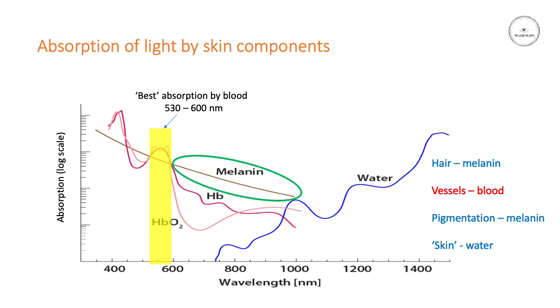If you want to treat hair, then you will target the melanin typically at this part of the spectrum — everything above around 600 nanometers. And this will, as you can see here, be preferentially absorbed in the melanin, but not so much in the hemoglobin or deoxyhemoglobin. So there's less chance of damaging blood vessels with this wavelength range.